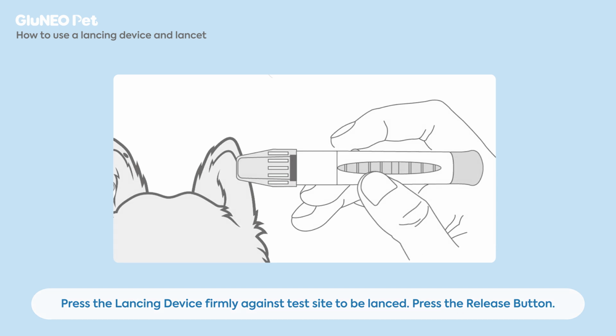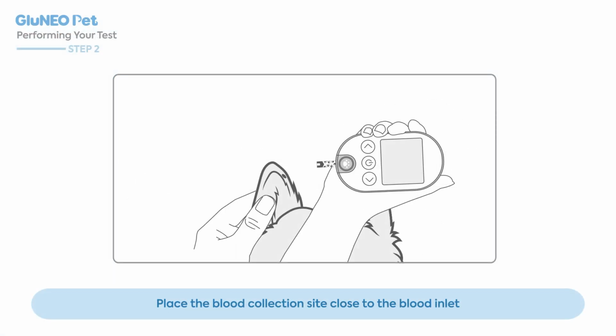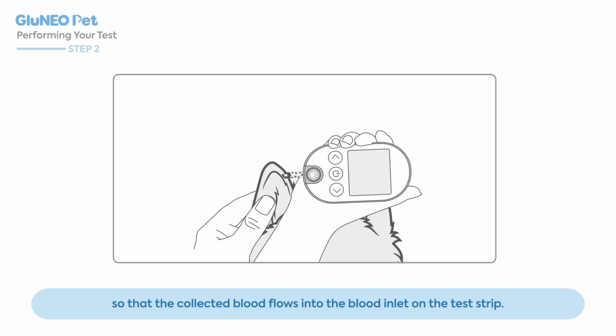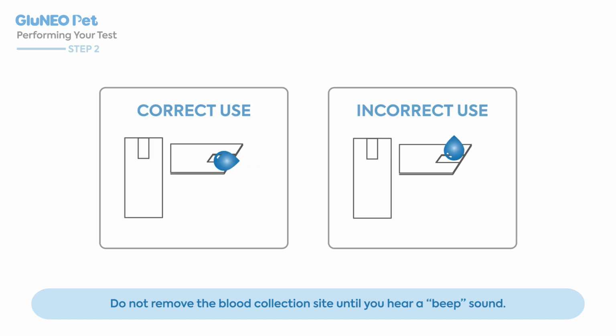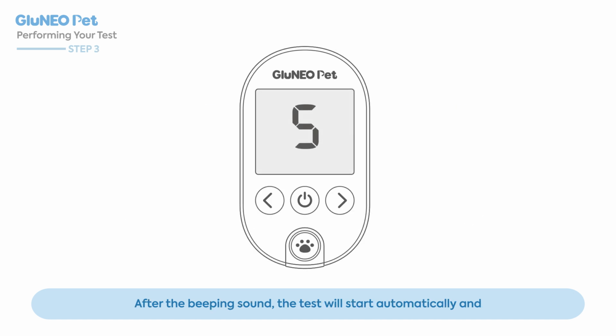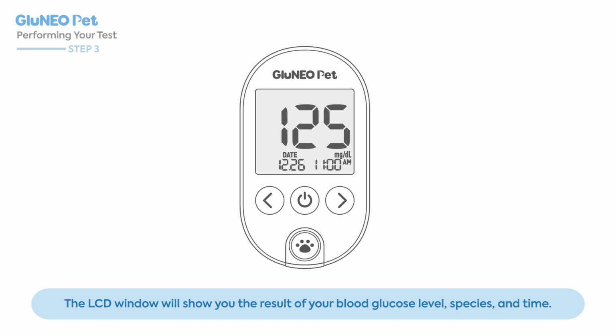Press the release button. Place the blood collection site close to the blood inlet so that the collected blood flows into the blood inlet on the test strip. Do not remove the blood collection site until you hear a beep sound. After the beeping sound, the test will start automatically and your test result will appear in 5 seconds. It will begin counting down from 5 to 1 second on the LCD display window. The LCD window will show you the result of your blood glucose level, species, and time.